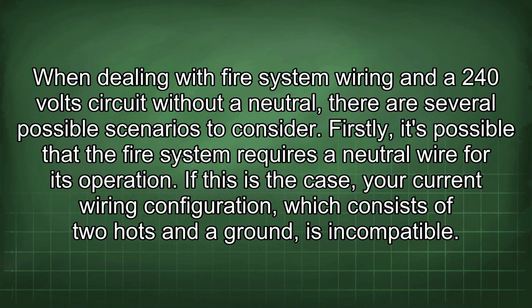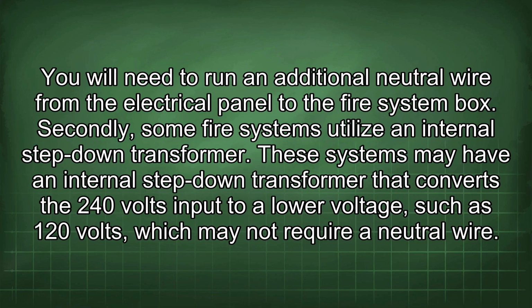When dealing with fire system wiring and a 240-volt circuit without a neutral, there are several possible scenarios to consider. Firstly, it's possible that the fire system requires a neutral wire for its operation. If this is the case, your current wiring configuration, which consists of two hots and a ground, is incompatible. You will need to run an additional neutral wire from the electrical panel to the fire system box.